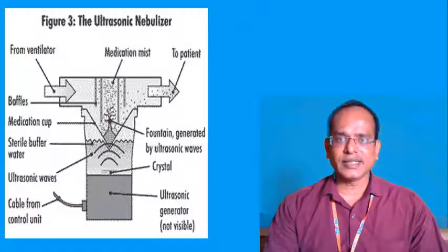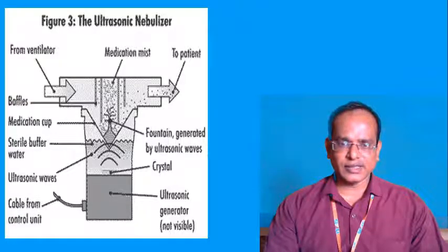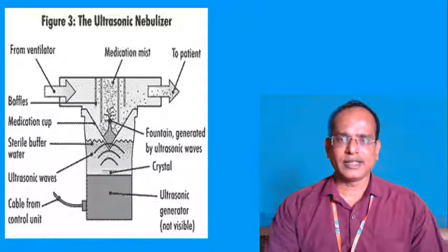Third one, we are seeing the ultrasonic nebulizer. So here the liquids are vaporized with the help of ultrasonic sound. This ultrasonic sound is created at the bottom of a chamber or reservoir that will create water molecules. Those molecules will reach the upper chamber. Finally, with the help of pressure or baffles, the medication or water vapor or drug molecules are reaching the patient.